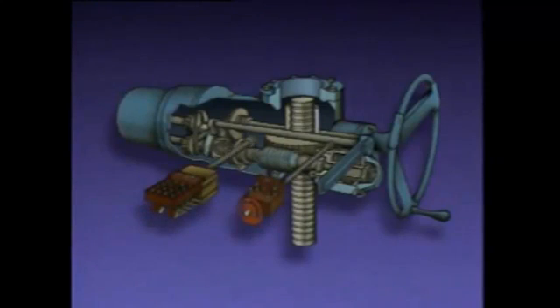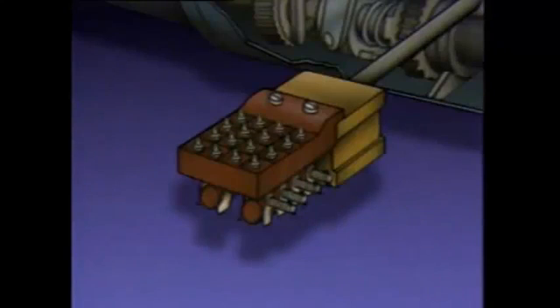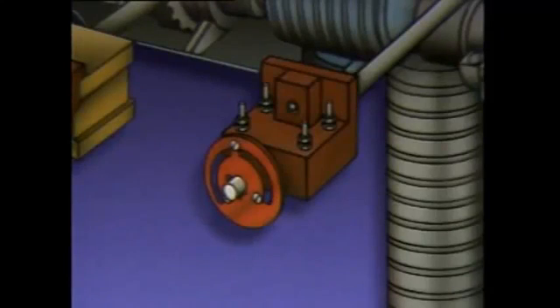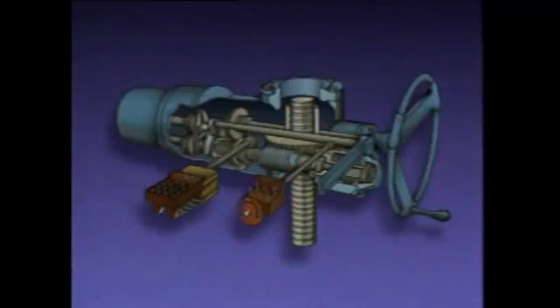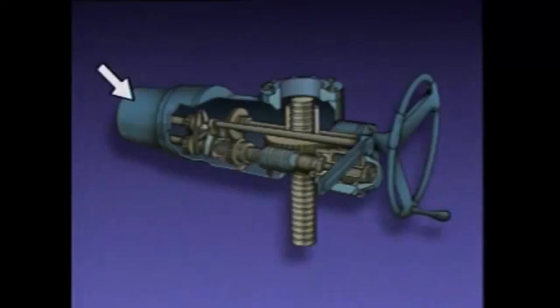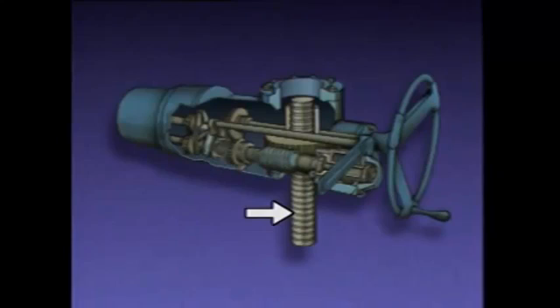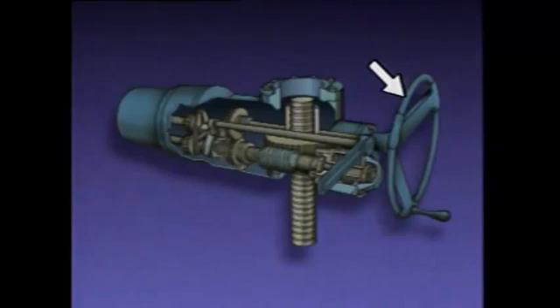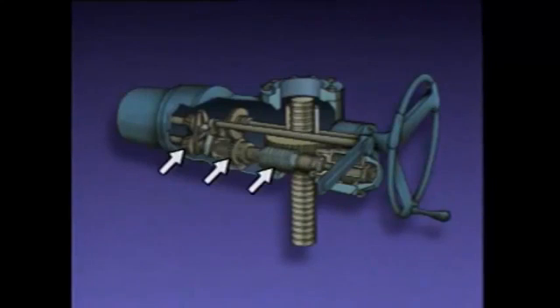This particular motor operator has two types of switches connected to its gears: a limit switch and a torque switch. When the motor operator is energized to reposition a valve, the motor drives the gears, and the gears move the valve stem. The lever is used with the hand wheel to position the valve manually in the event of a problem. Depressing the lever disengages the motor from the gearing and connects the hand wheel to the valve stem through part of the gearing.